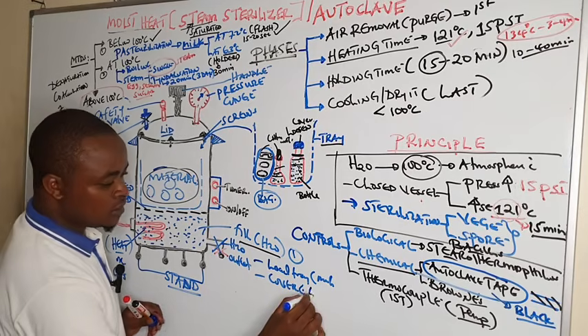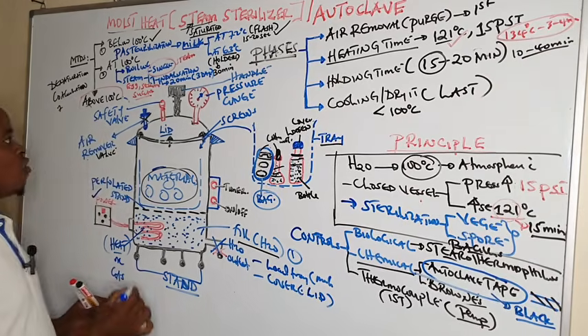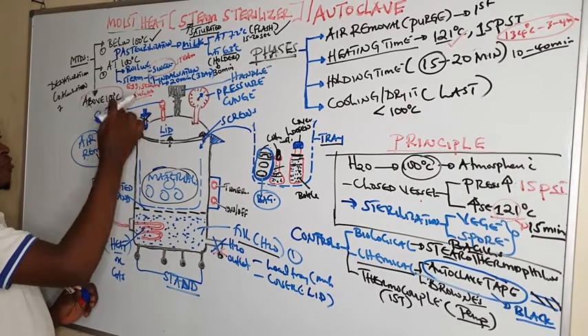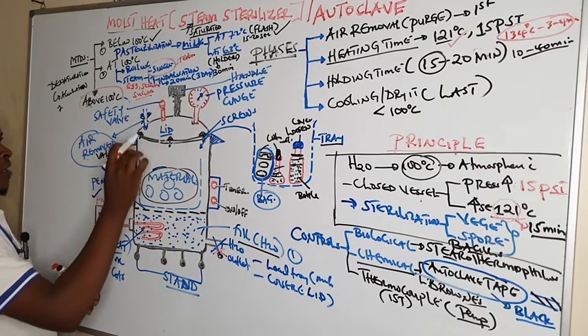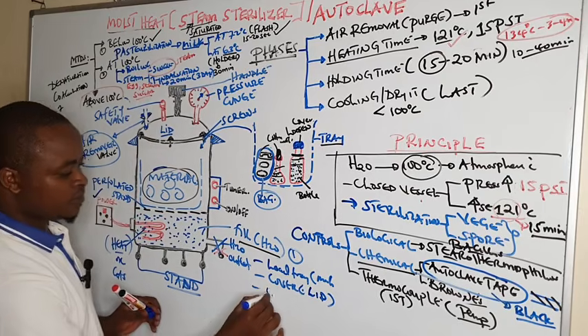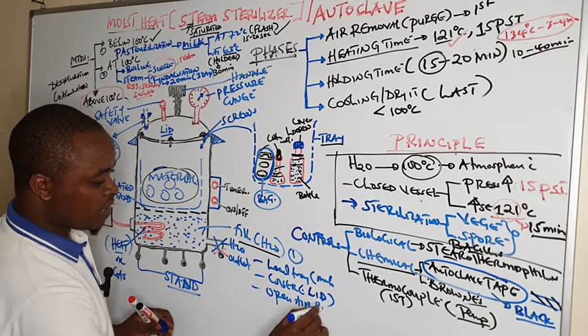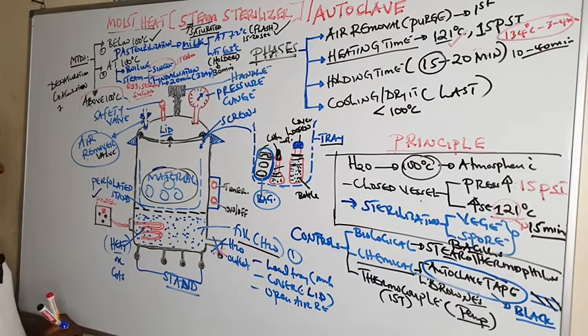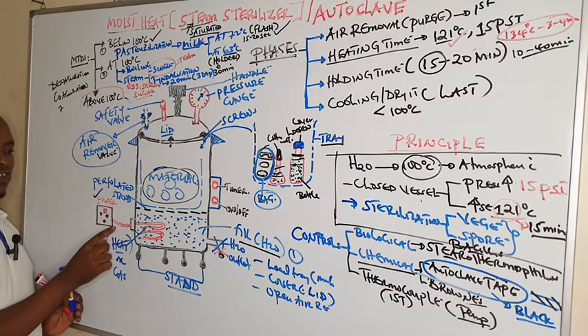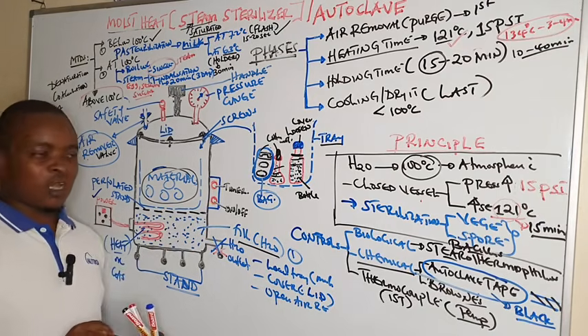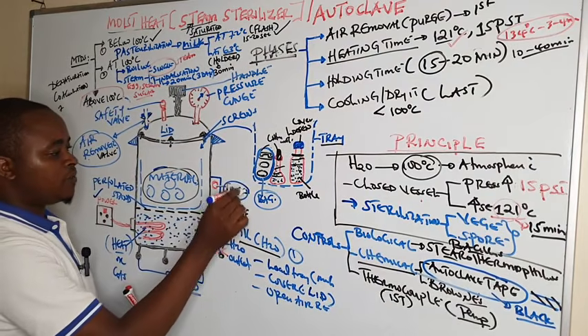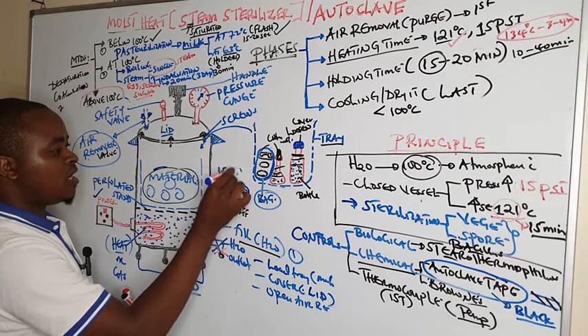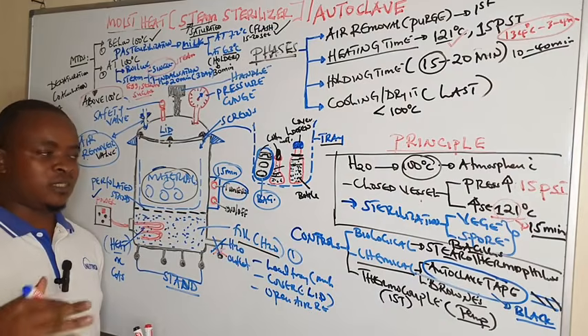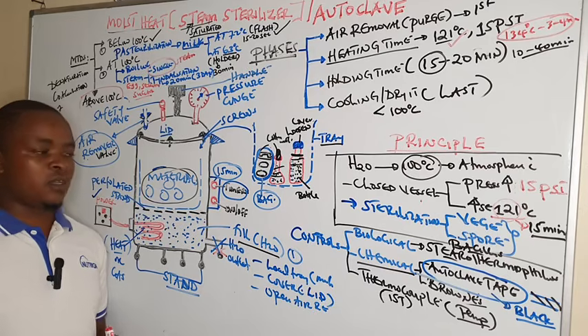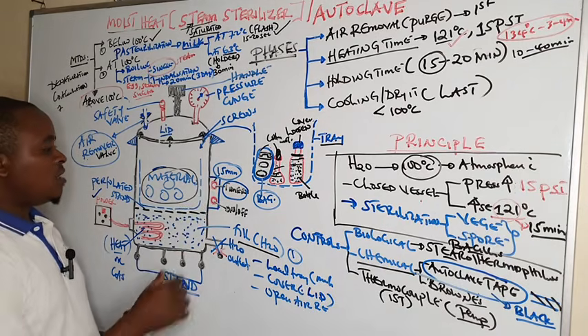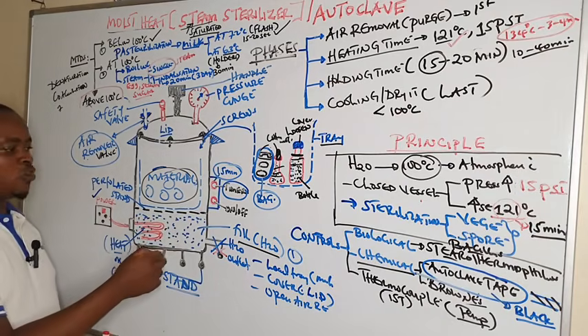After securing the lid tightly, you open the air remover first. So open the air remover, or the air valve. After opening it, switch on from the power source. After switching on the autoclave, press the on button. After pressing the on button, set the timer. The holding time is 15 minutes, but depending on the materials being autoclaved, it can go up to 20 or even 30. After timing, when the water starts boiling, it is going to produce steam.